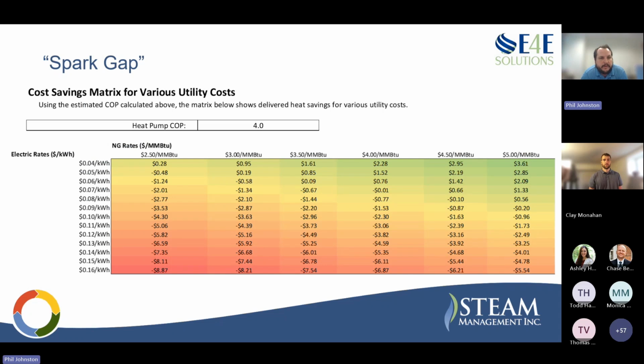Clay hinted at this as well. A big driver of whether a heat pump will be viable or not is cost. And a phrase you'll hear often in these discussions is spark gap. All that is, is the difference in cost of natural gas versus cost of electricity. So when you change from a steam or any kind of gas-fired system to a heat pump, what you're essentially doing is replacing that gas energy as a fuel with electricity. And so the cost is a big part of that.